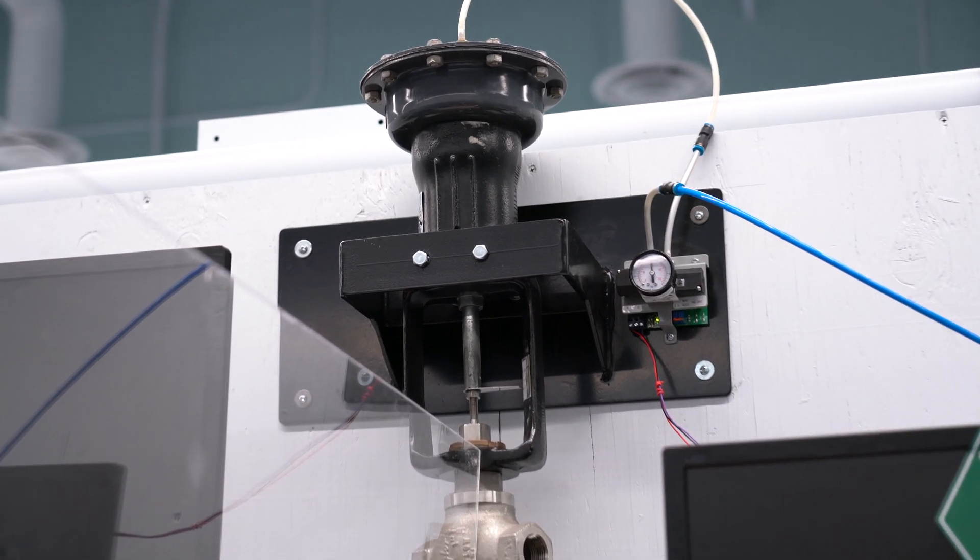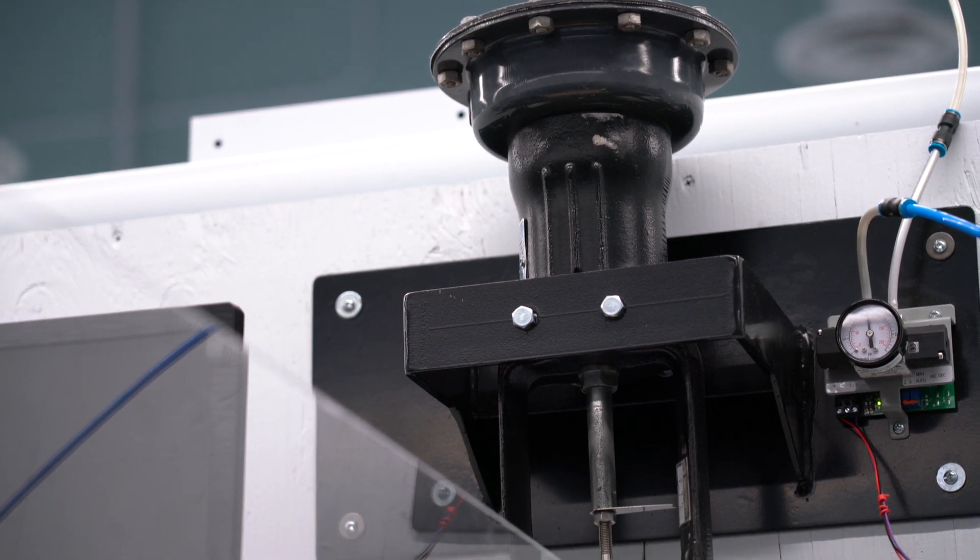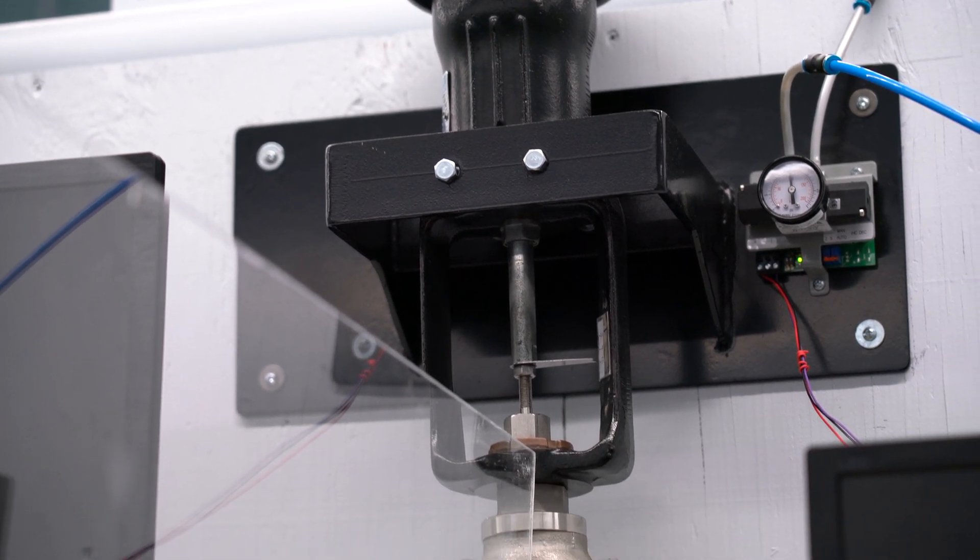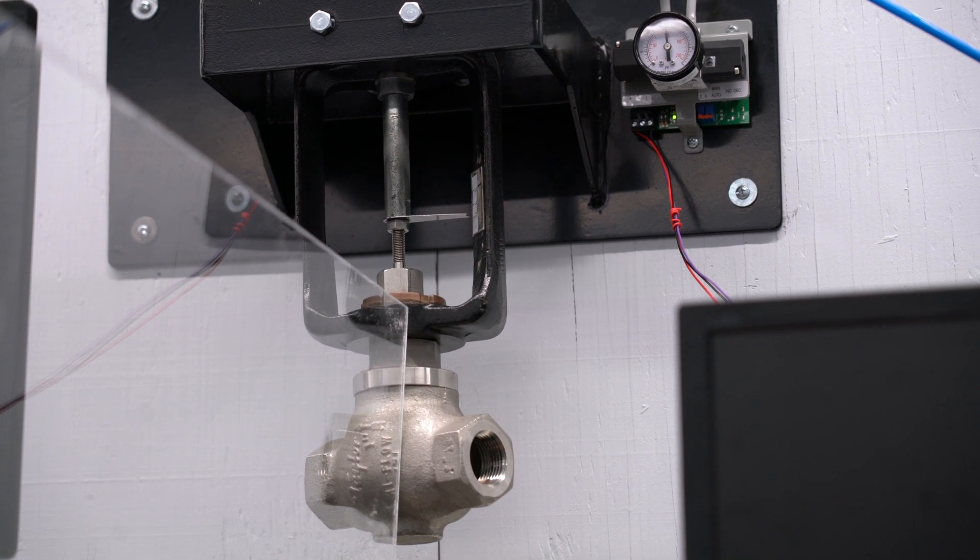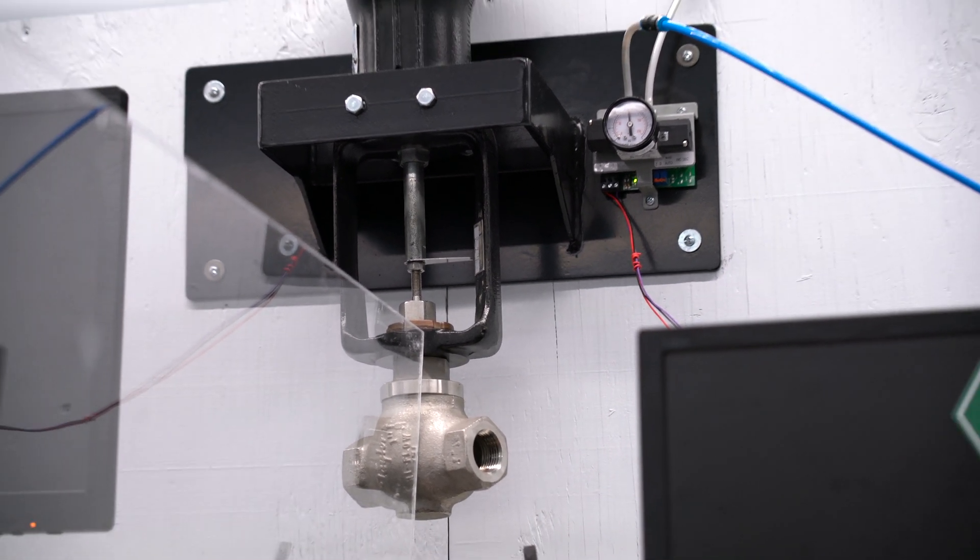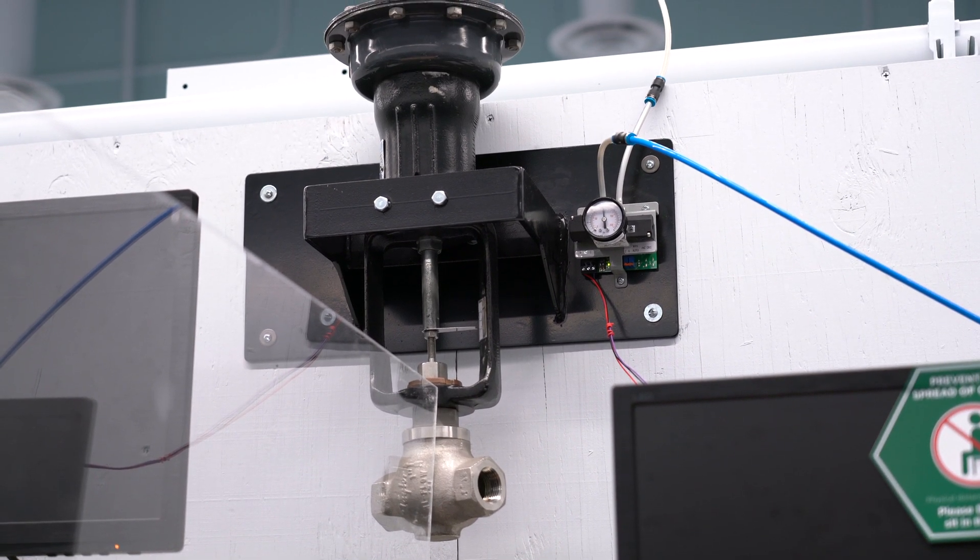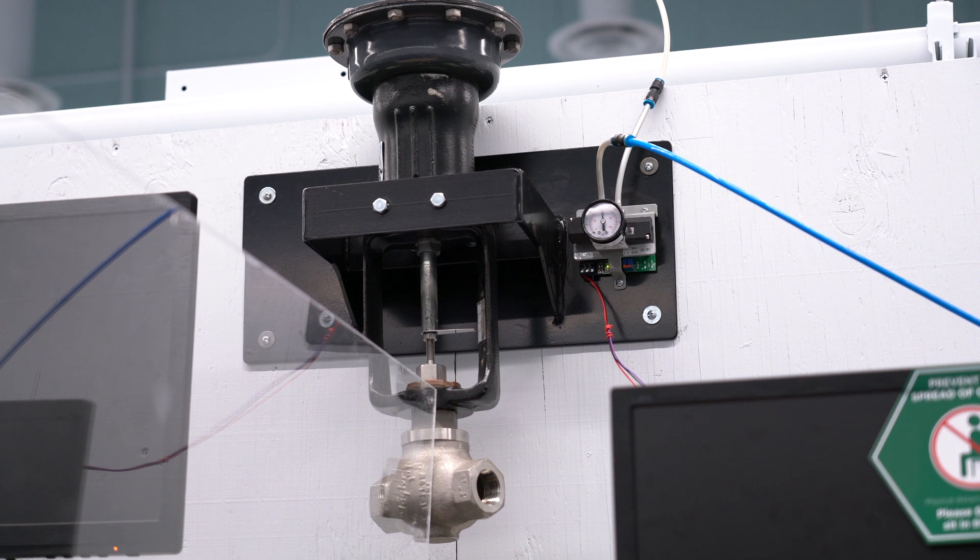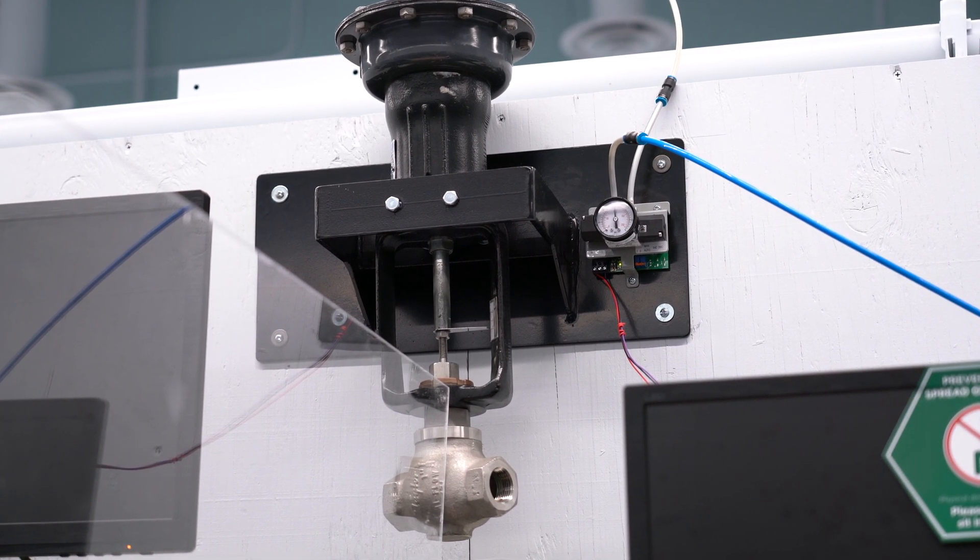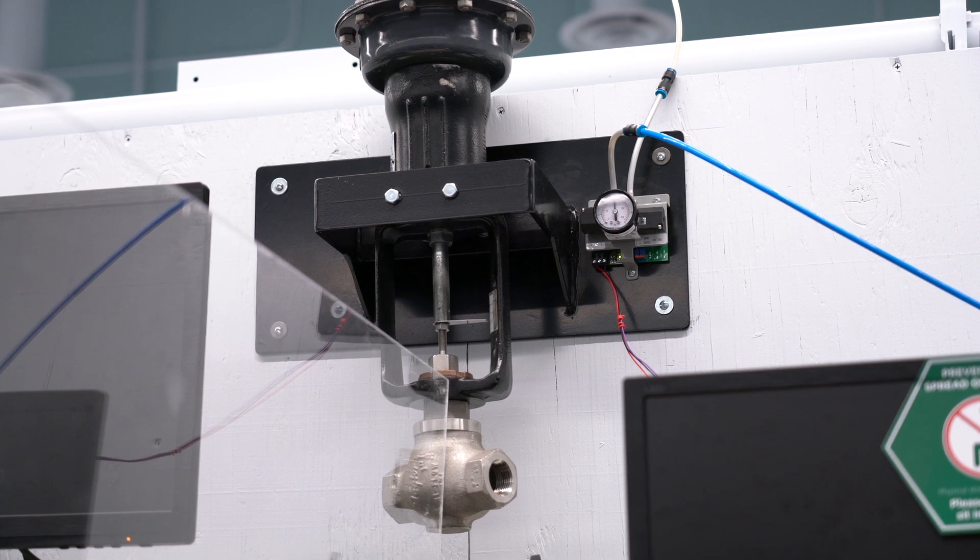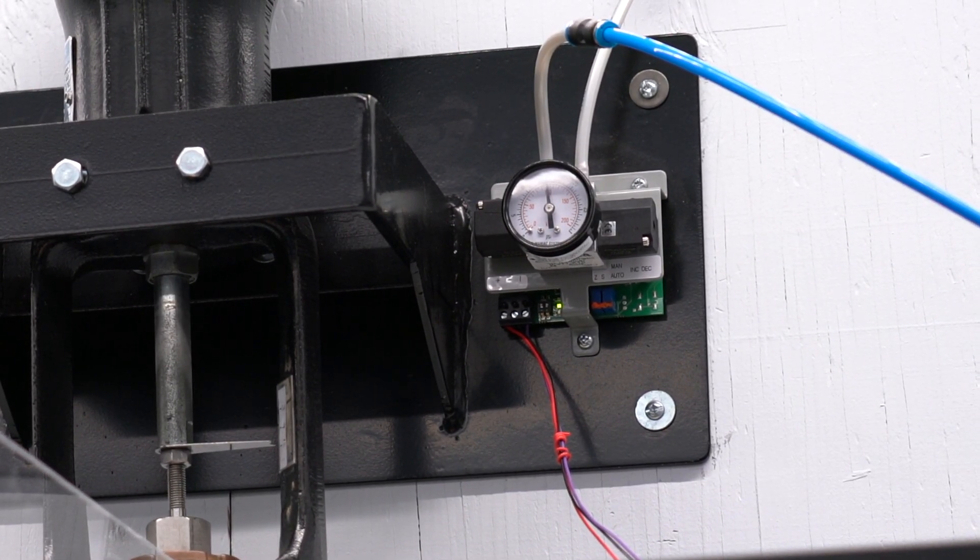Now if we want to control this with a programmable logic controller, we have to convert an analog signal to a pneumatic signal. So that's what this little device to the right is doing. It's called an electro-pneumatic transducer. It converts an electrical signal to a pneumatic signal, and the electrical signal range is 0 to 10 volts, and it converts it to a pressure in the range of 3 to 15 psi.